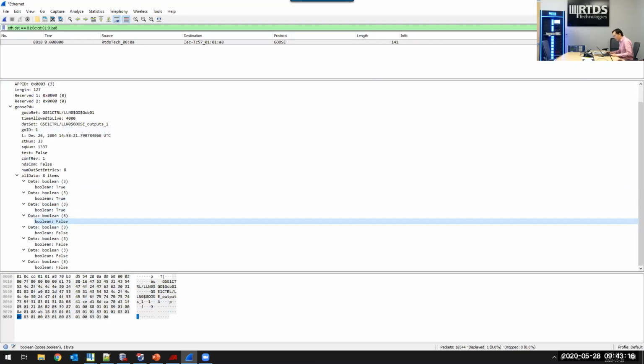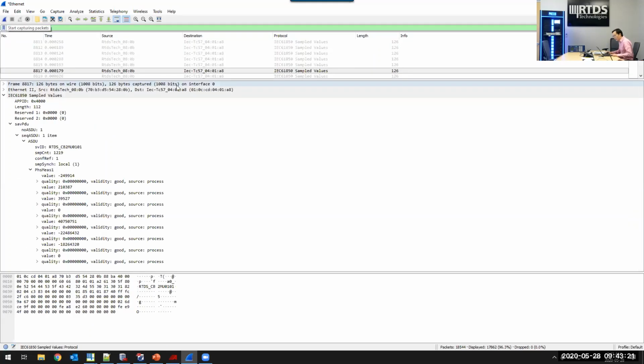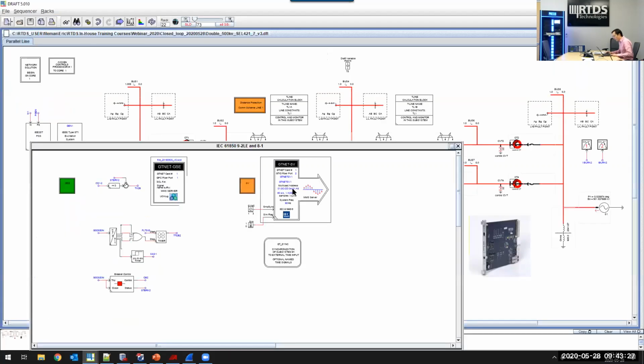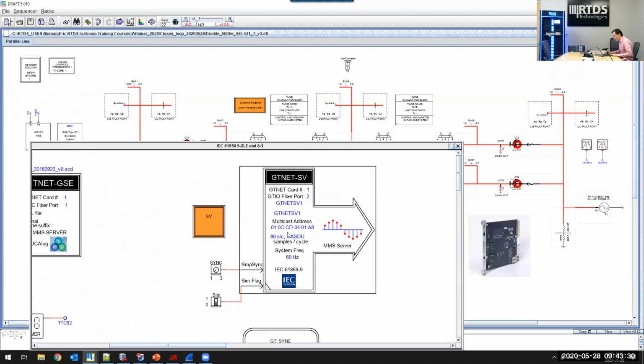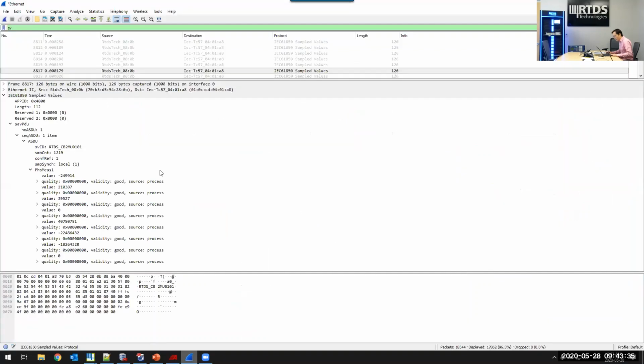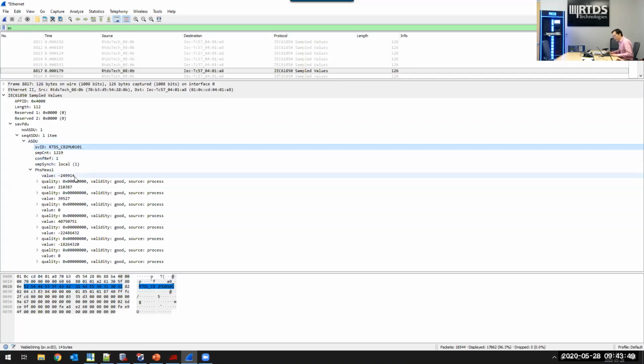And also you can verify your sample values. If we go back to our configuration, we know that GTNet is configured to send the SV packets to 0401A8. Now back to Wireshark, after entering SV as a filter, we have this 0401A8 here. Now we can see this is our message. We have the same SV ID that was configured in the GTNet, and there should be 8 data entries here, 4 for currents and 4 for voltages.